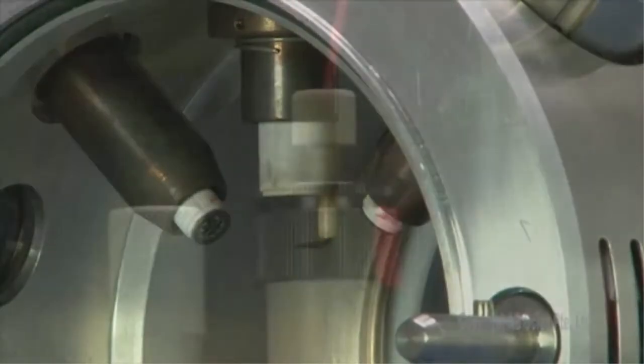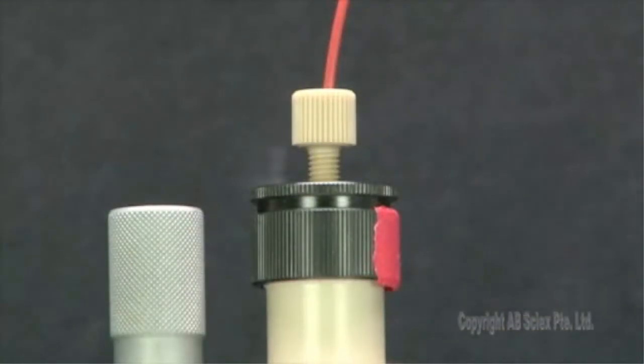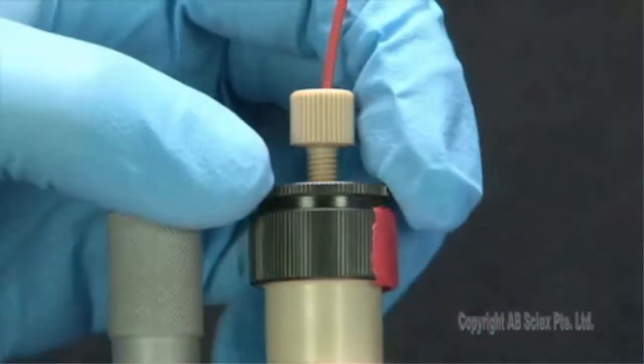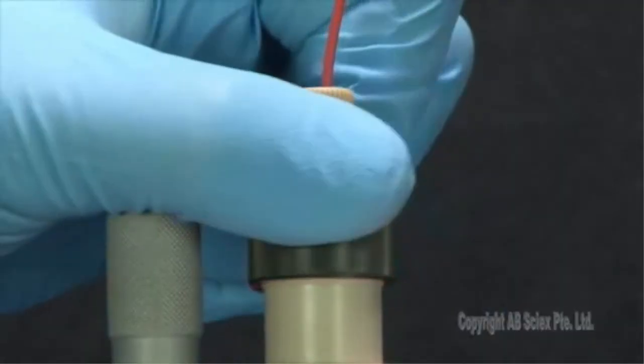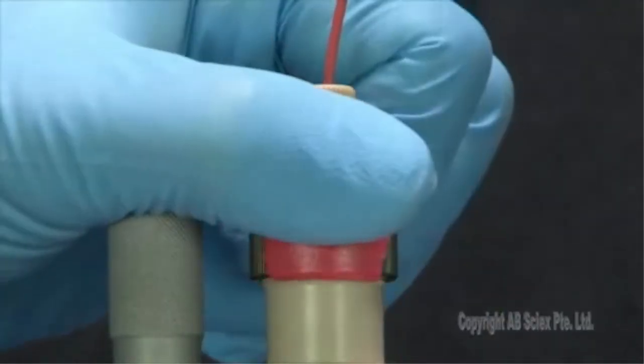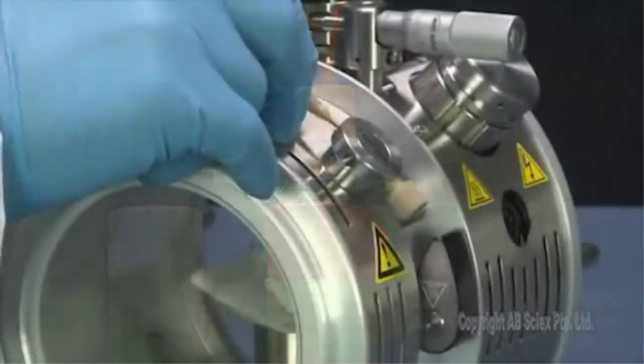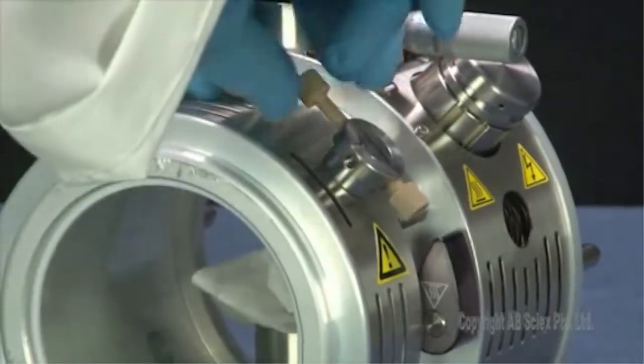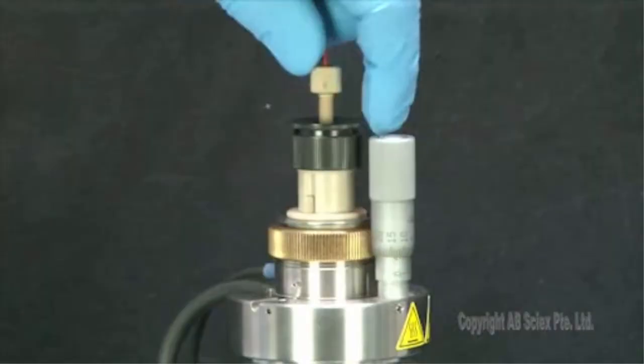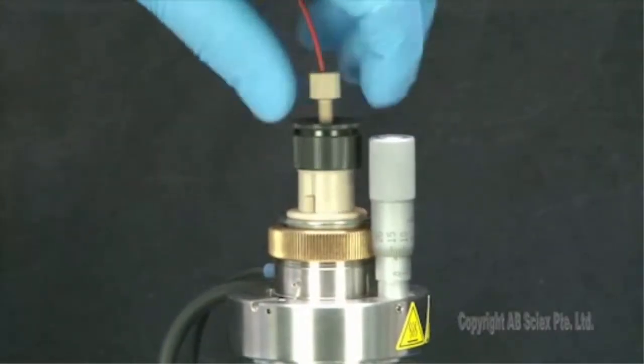If the electrode was retracted or a new electrode was installed, then adjust the black adjustment nut on the top of the probe to adjust the electrode tip. This distance can be flow rate dependent. Insert the sample tubing and finger-tight PEEK fitting into the port at the top of the probe and then tighten until finger tight. Make sure that the tubing ends are flush with the seat of their connections.